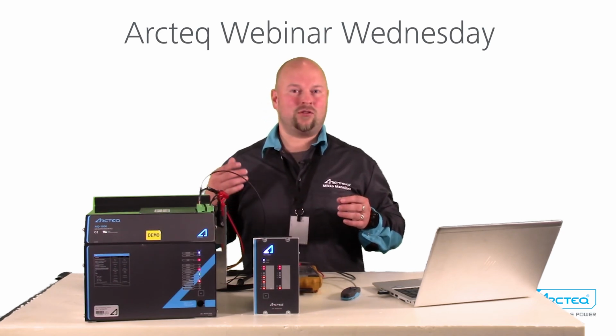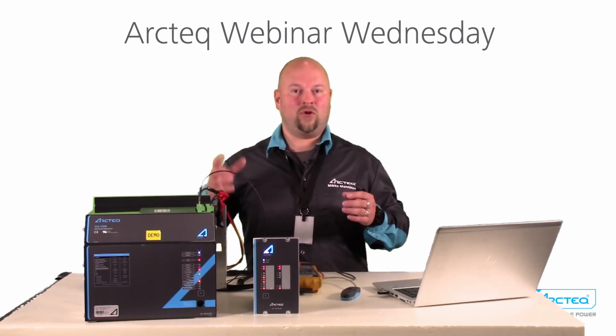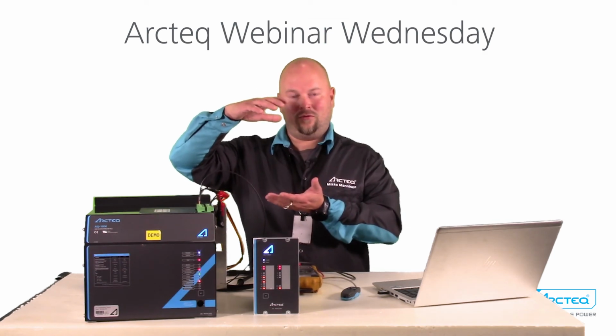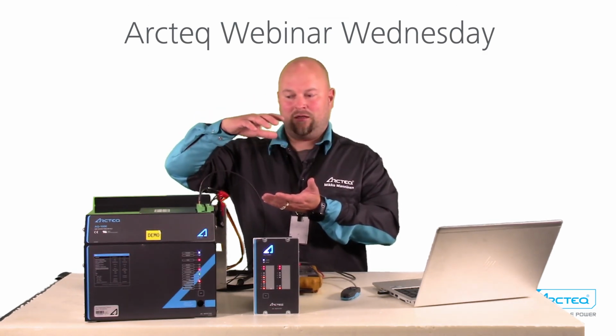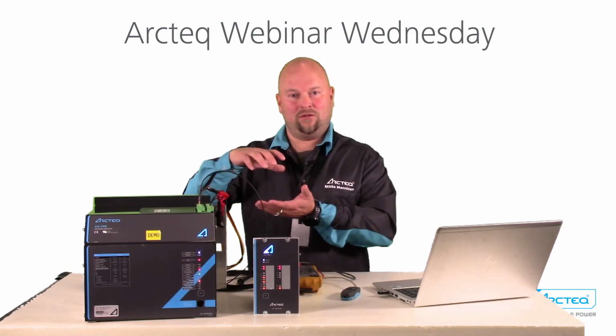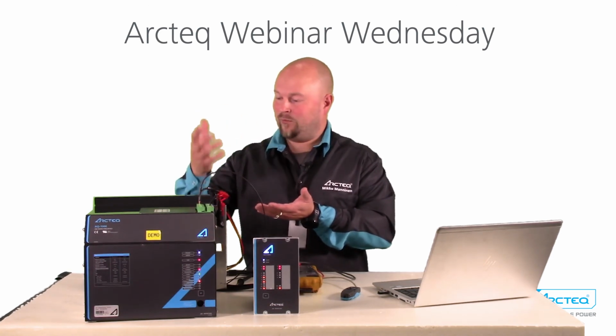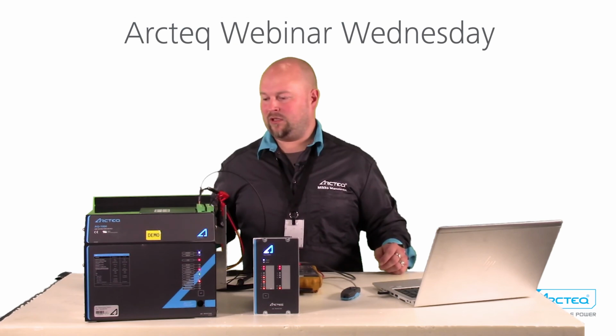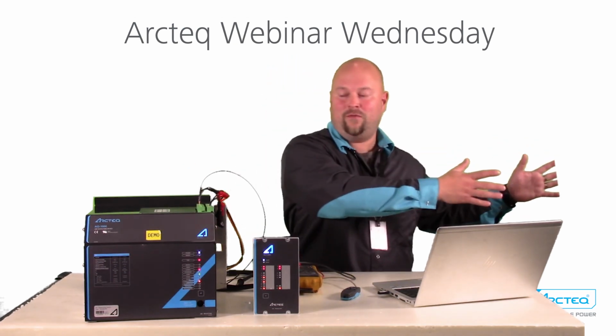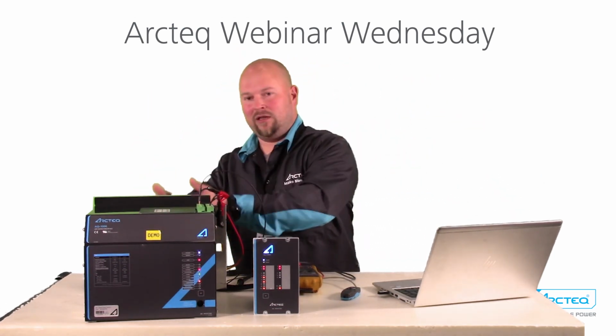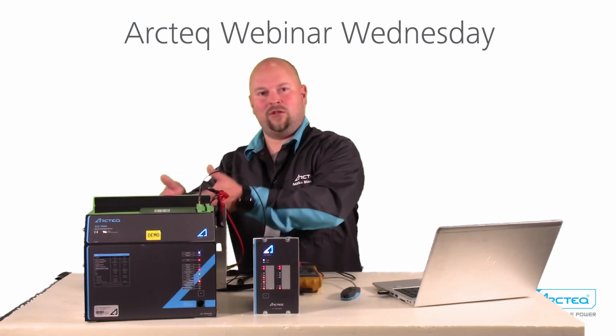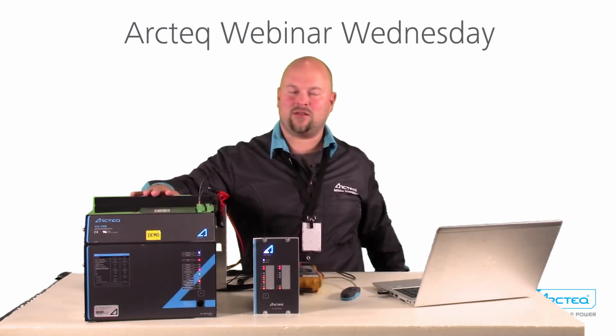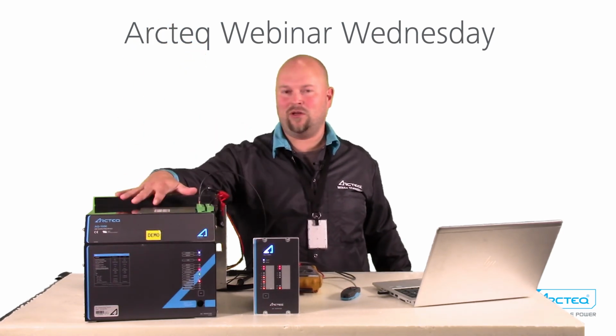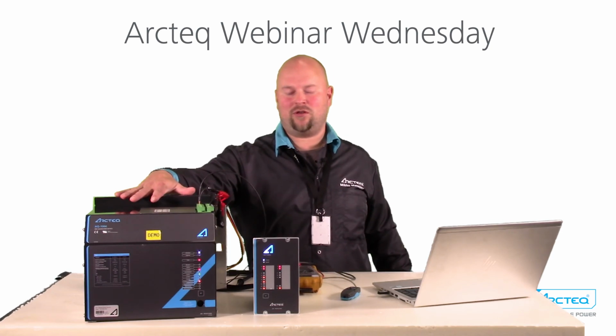And when the short circuit is pure, then the voltage will drop quickly to a very low level, close to zero. And then the current will transfer from the fault immediately to this unit, because it has only micro ohms. After the incomer circuit breaker, this has only micro ohms, a very pure short circuit, and the fault transfers to this unit.